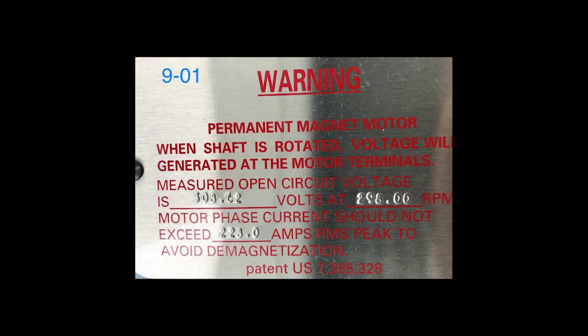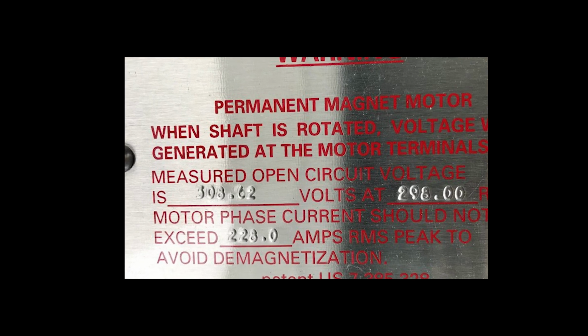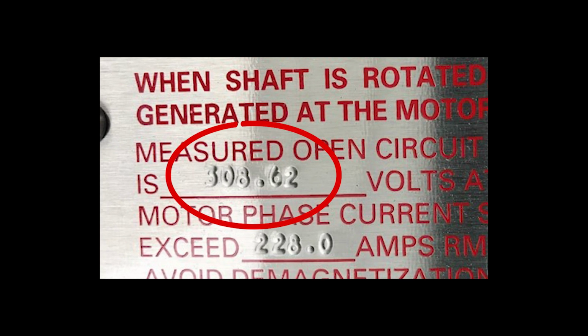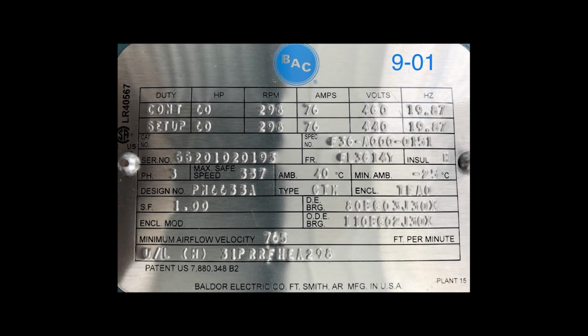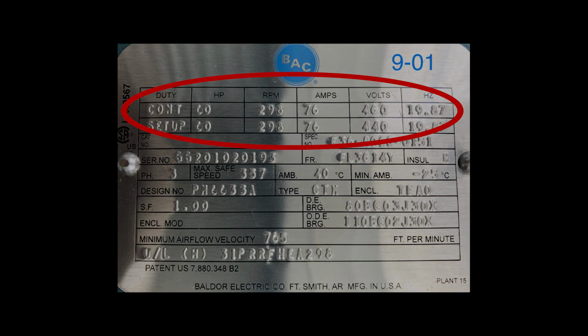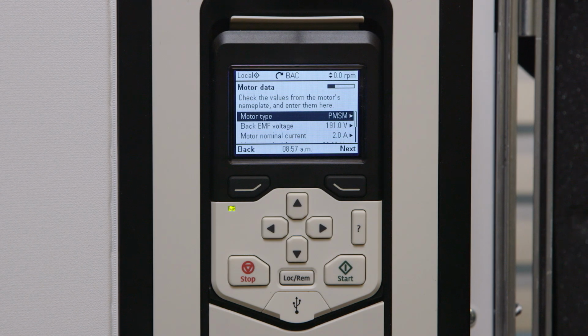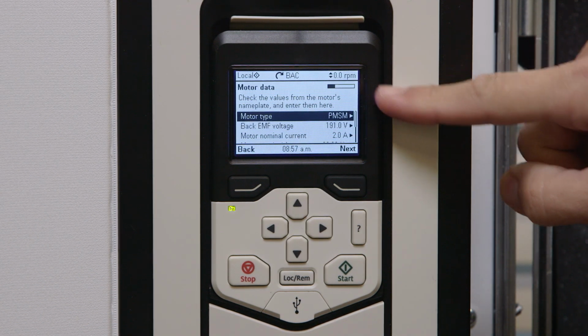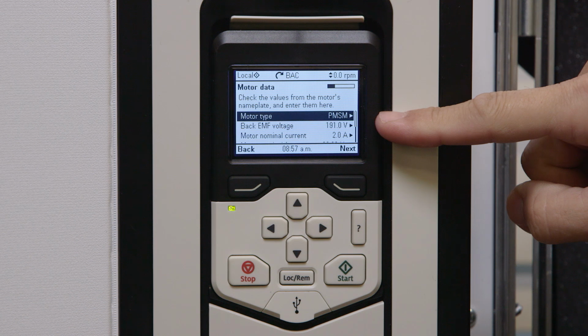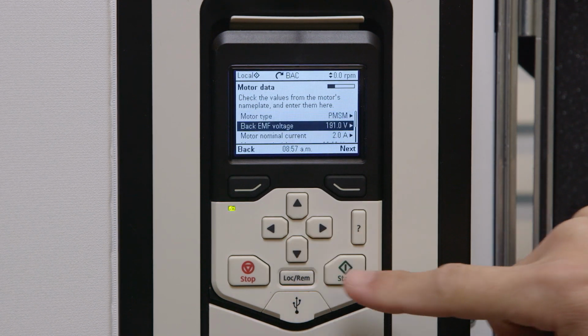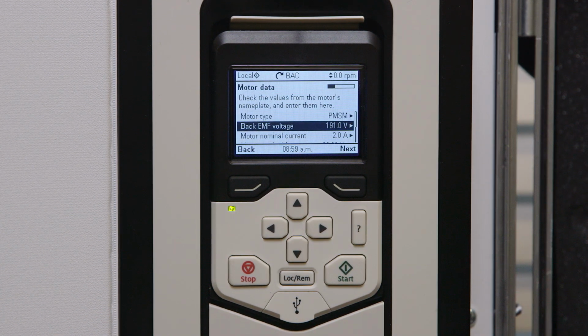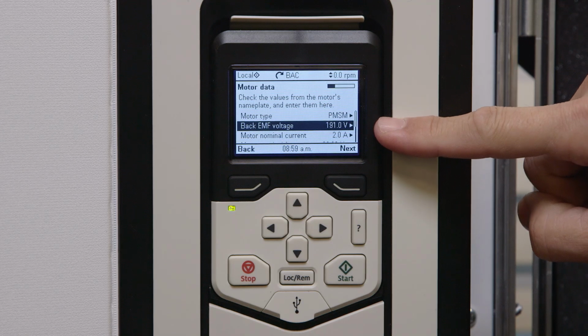Before starting, find the photo of the warning label and the EMF value you recorded earlier. Also, find the photo of the nameplate and the nameplate values that you recorded earlier. Remember to use the values on the setup line. Ensuring the display is in motor data mode, leave the motor type on the PMSM selection and press the down arrow. Now, let's enter the back EMF voltage.